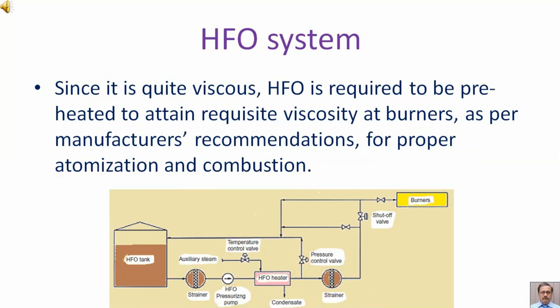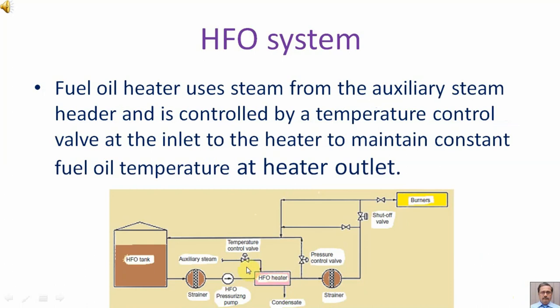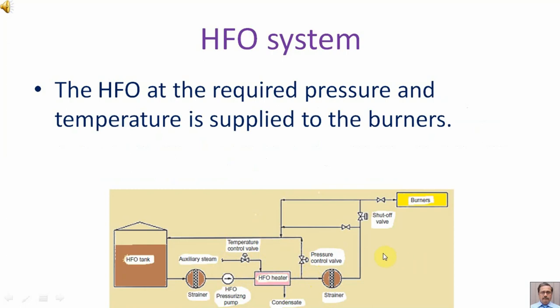Since HFO is quite viscous, it is required to be preheated to attain the requisite viscosity at burners as per manufacturer's recommendations for proper atomization and combustion. The fuel oil heater uses steam from the auxiliary steam header and is controlled by a temperature control valve at the inlet to the heater to maintain constant fuel oil temperature at the heater outlet. The HFO at the required pressure and temperature is then supplied to the burners.